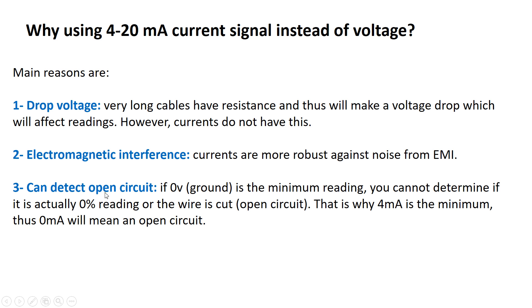Third, can detect open circuit. Now if you consider zero volts or ground to be the minimum reading, you cannot determine if you actually read zero percent from your sensor or actually the wire is cut or open circuit. And this is why 4 milliamps is the minimum, thus zero milliamps will mean an open circuit.